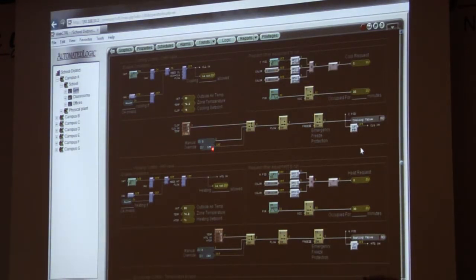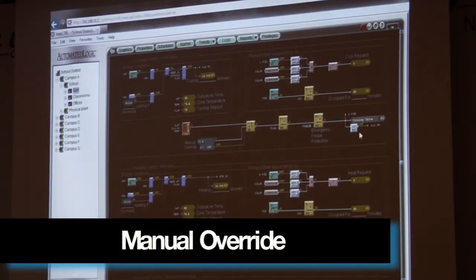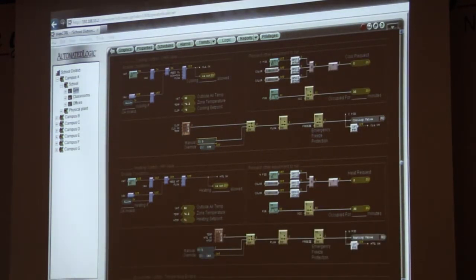But I want to show you something else. This has been included in all of your software for you guys. You see the hot water valve and the chill water valve. We always want to make sure that safeties are in there, that the unit is as safe as possible. So even though you can lock outputs, we've added these. If you look through, you're going to see on both of them, the manual overrides. Rather than locking the output right here, you can come inside here and say, here, I have 2 microblocks.